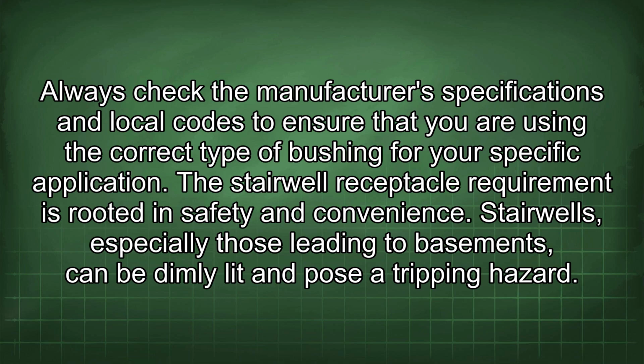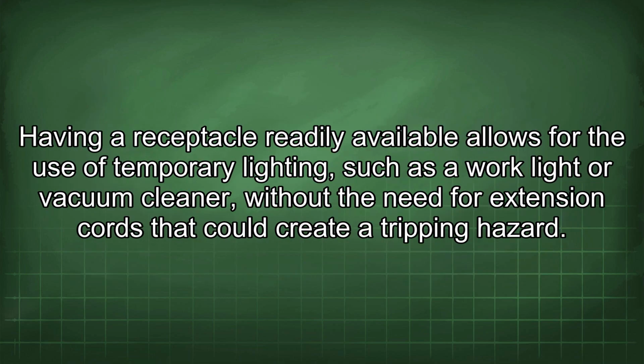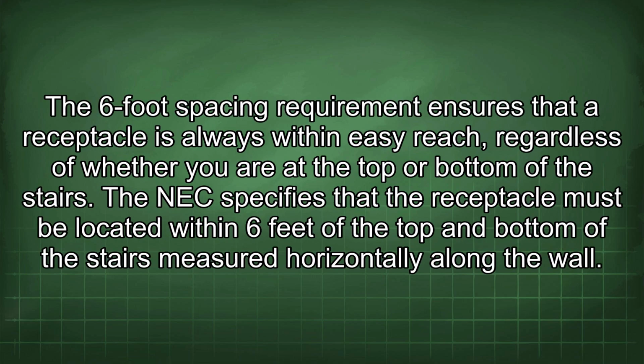The stairwell receptacle requirement is rooted in safety and convenience. Stairwells, especially those leading to basements, can be dimly lit and pose a tripping hazard. Having a receptacle readily available allows for the use of temporary lighting, such as a work light or vacuum cleaner, without the need for extension cords that could create a tripping hazard. The 6-foot spacing requirement ensures that a receptacle is always within easy reach, regardless of whether you are at the top or bottom of the stairs.